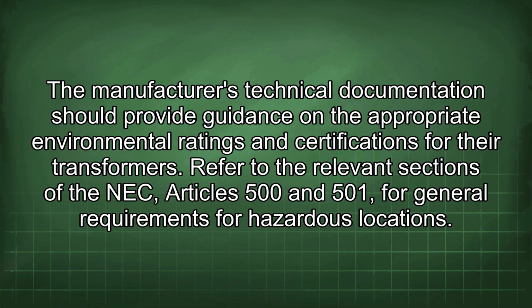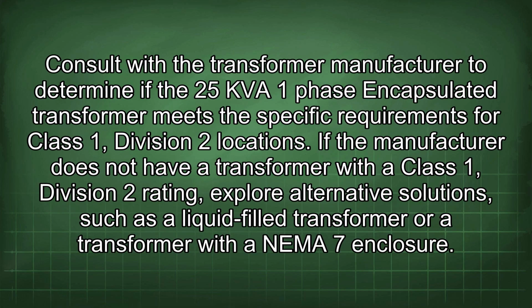Refer to the relevant sections of the NEC Articles 500 and 501 for general requirements for hazardous locations. Consult with the transformer manufacturer to determine if the 25 kVA one-phase encapsulated transformer meets the specific requirements for Class 1 Division 2 locations. If the manufacturer does not have a transformer with a Class 1 Division 2 rating, explore alternative solutions such as a liquid-filled transformer or a transformer with a NEMA 7 enclosure.